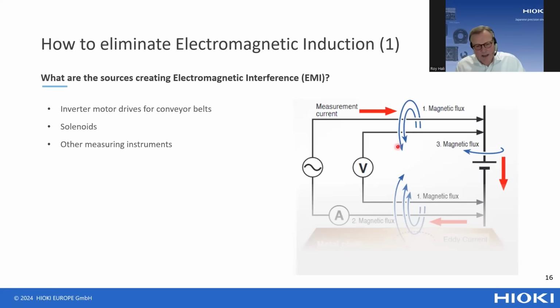This AC current causes a magnetic flux, and that magnetic flux can be picked up by the sense wire, inducing a voltage in the sense wires that will interfere with the measurement signal if the right precautions aren't taken. Besides that, there is also magnetic flux in the production line itself due to electromagnetic interference from, for instance, inverter drives, solenoids, or other measuring instruments. This can also induce a voltage on the sense wire, and that's what you have to overcome.